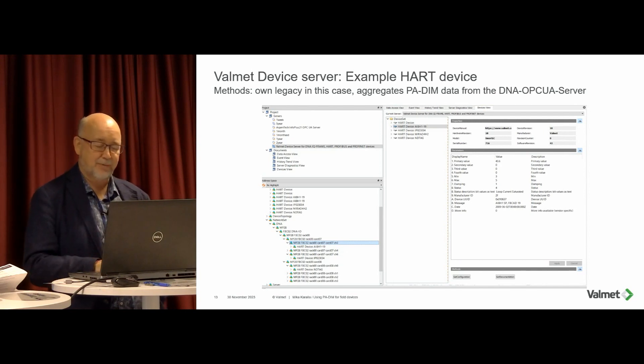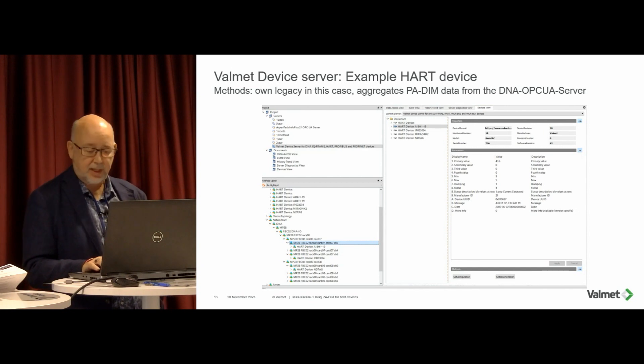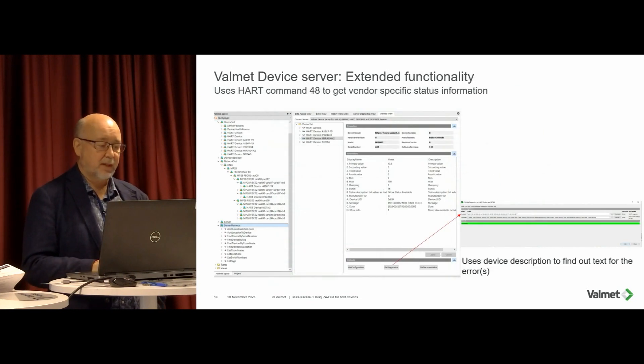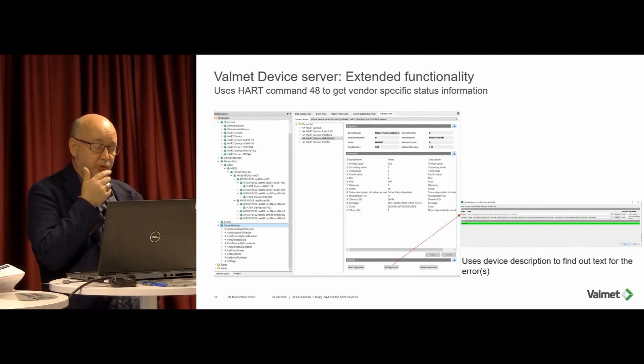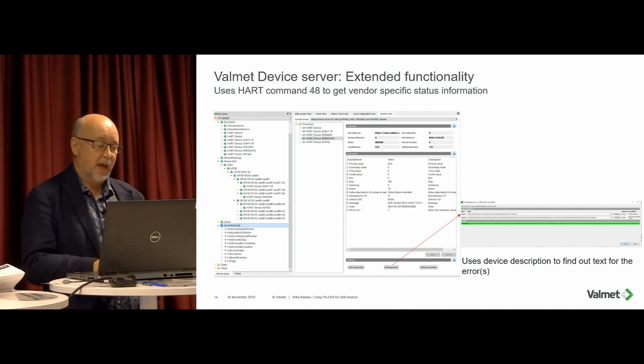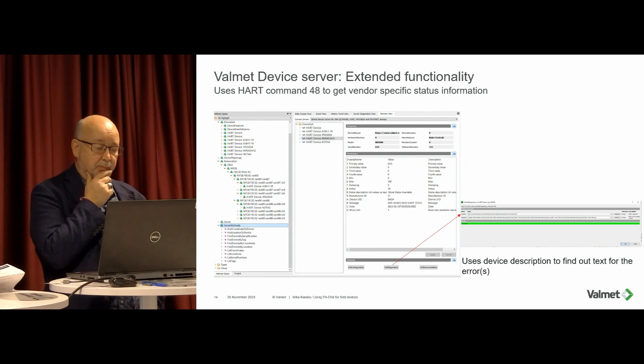I have also extended this a little bit. I use HART command 48 to get vendor-specific status information — I think it's a clever implementation but I was just experimenting. I added a method to get the diagnostics, which returns the HART reply as a byte string. I have also added how to translate those bytes and bits into meaningful human-readable descriptions.